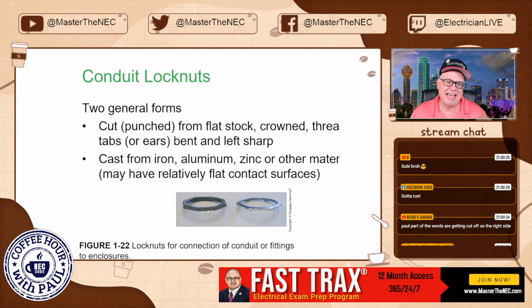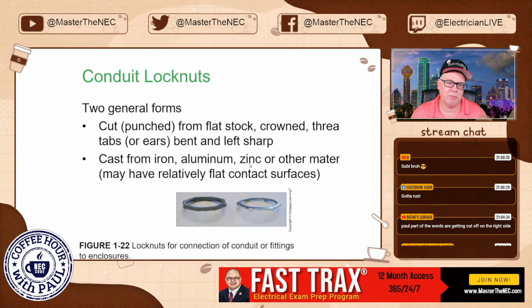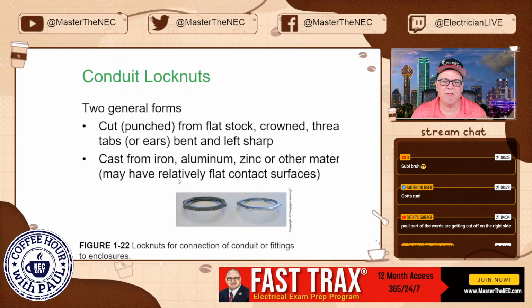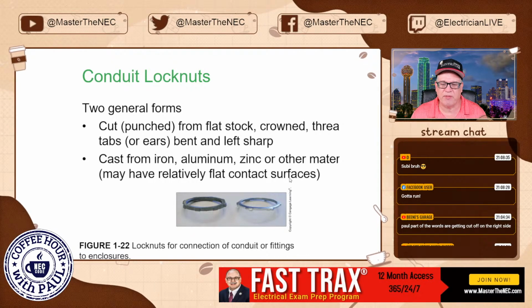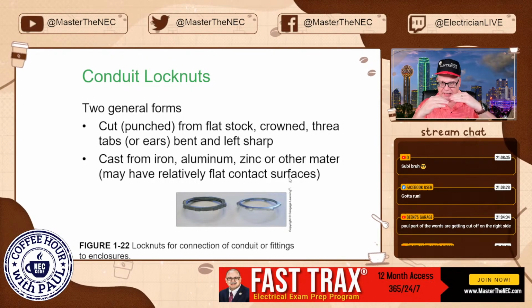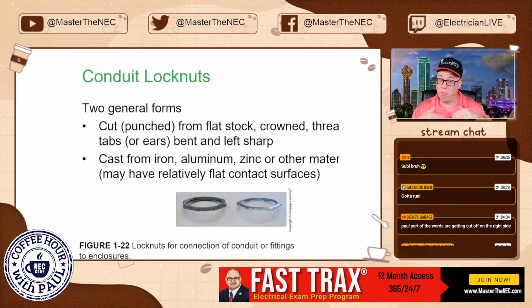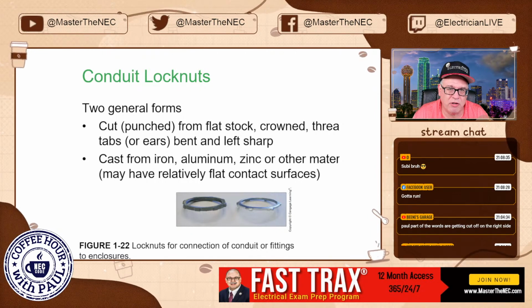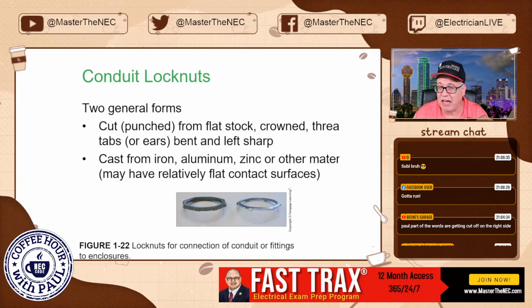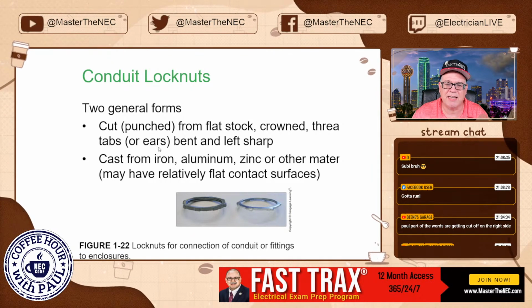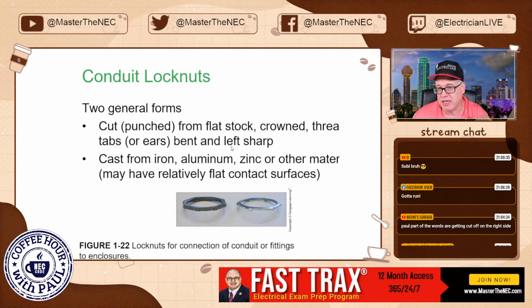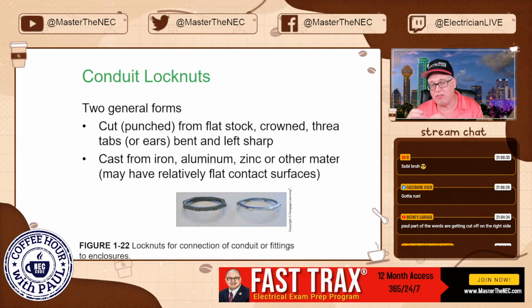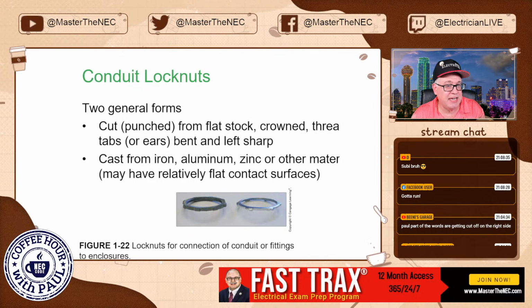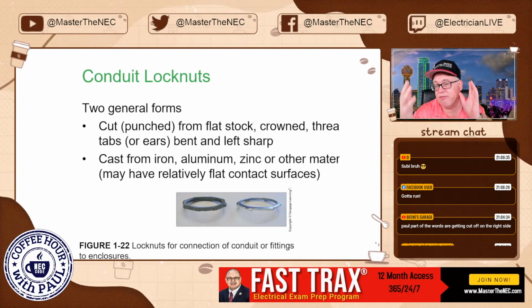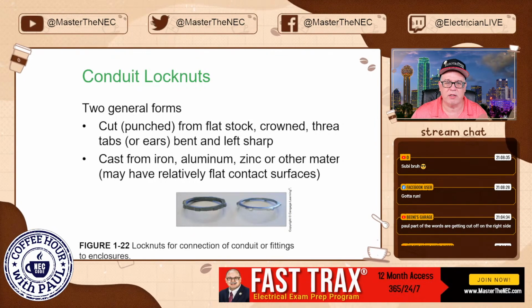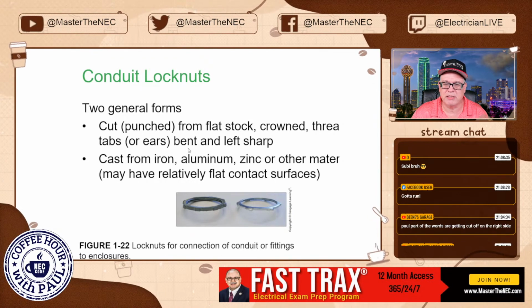And then you got these that are cast, and these are cast from iron, aluminum, zinc, or other material, and may have relatively flat surfaces. They are not going to bite into any material. So it's going to be even more imperative that you make sure that you get rid of any paint or surfaces that are non-conductive. Whereas you might have a lock nut that actually will bite down into the material and tie that threads to that lock nut, to that fitting, to that raceway, tying everything together, give you the best chance of clearing an overcurrent on a fault condition, right?